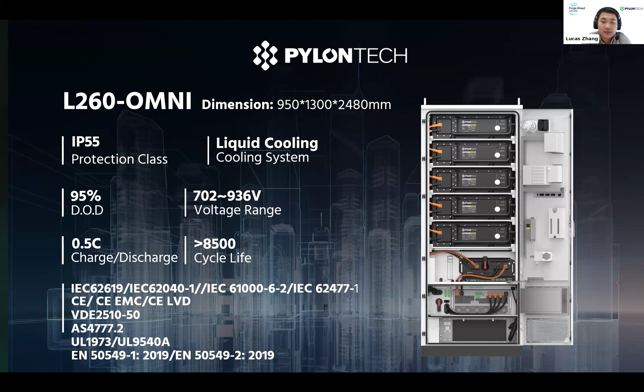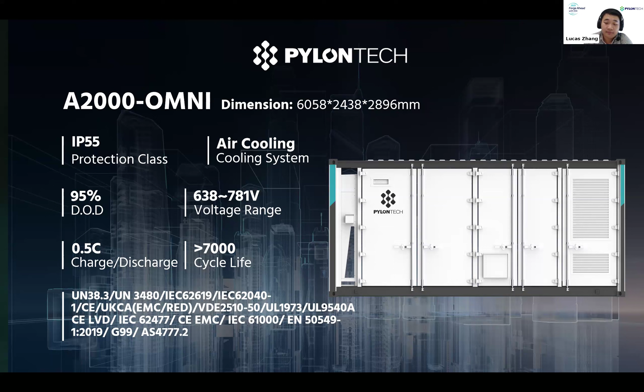The next solution is what we call A2000 OMNI. Namely, this is an air cooling containerized solution with 2 megawatt-hours of battery capacity. Inside it is also coupled with 2 500K SINEXCEL PCS cabinets. In total, it's a 1 megawatt and 2 megawatt-hour half-C solution. The protection class is also IP55, and we use forced air cooling with 2 HVAC on the side. The depth of discharge, the DoD level, is also 95%, and the voltage range is below 1000 volt DC. The cycle life is over 7,000, and we have similar certifications such as IEC, UN, CE, VDE, and UL.